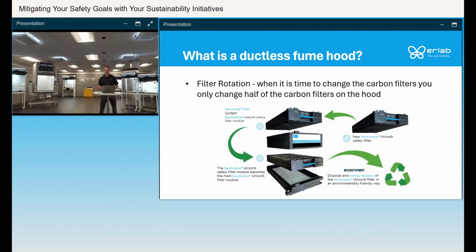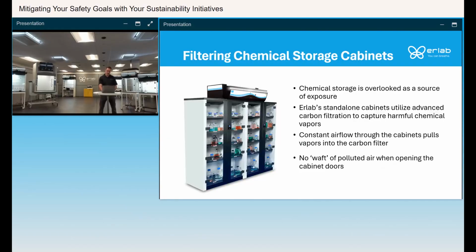And when you dispose of the filters, we recommend high temp incineration. They're basically regulated non-hazardous waste. So if you have an on-site hazardous waste provider, they can typically dispose of the filter for you. And if you don't, you can basically just put that filter back in that same box and bag that the new filter arrived in. You put that used filter in there and UPS it back to us. And it's about $75 a filter to dispose of if you go that way.